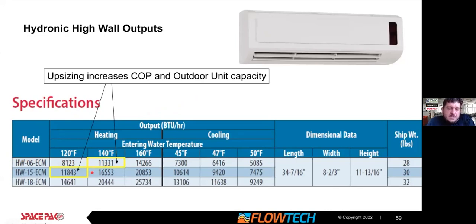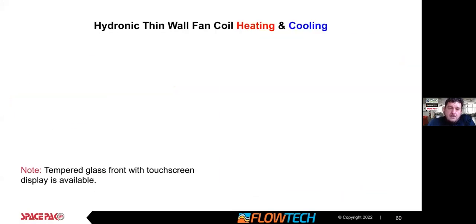It's a minor cost to upsize a unit, and you're able to drop your water temperatures down to 120 and still satisfy that 11,000 BTU load. The physical dimensions on these units are all the same, so it's not going to take up more space. I say this because it's a design strategy: is the goal to reduce that water temperature? Similarly, you could even upsize more to get down to 110 degree water. Once we drop those water temperatures, our outside SpacePak unit is operating much more efficiently and has a greater capacity. So design flexibility, have a look at that.